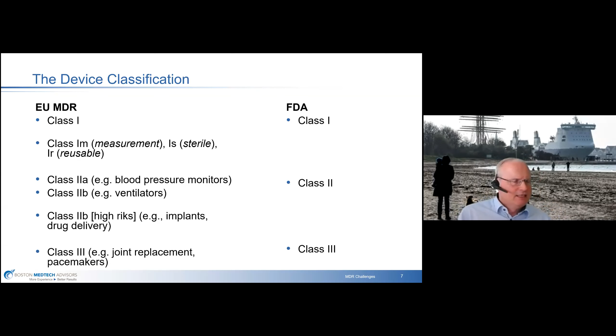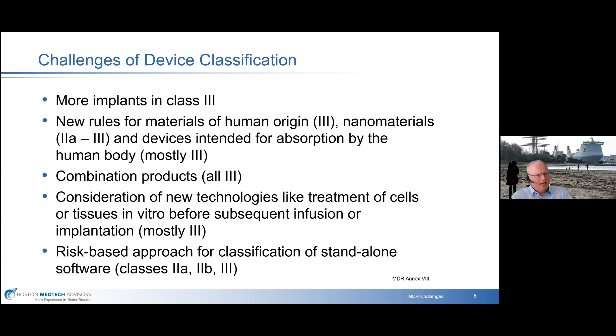Now, we already had these classes, basically, class 1, class 1A, class 2A, 2B, and class 3 under the old medical device directive, which many of you may know. But with the MDR, with the medical device regulation, we have now more implants in class 3 than before. We have new rules for materials of human origin, which places many more devices into class 3. Nanomaterials have been introduced into the MDR, and depending on the exposure of the patient to the nanomaterials, it may be class 2A, class 2B, or even class 3. Or devices intended for absorption by the human body. These are mostly class 3 devices.